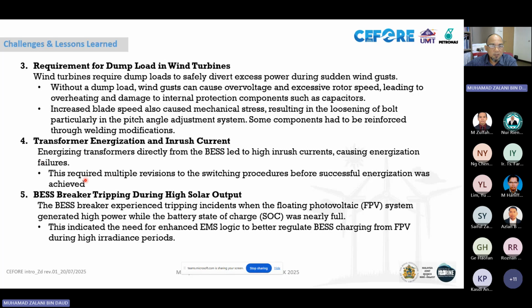Number 4 is about the transformer energization and inrush current. At the beginning of the commissioning stage, we need to energize the transformer. This transformer is a 500 kVA transformer, and we have the battery energy storage from MJB to energize this transformer. Inside the battery energy storage from MJB, they have an isolation transformer which is half the size of our transformer. So during energization, we failed. The system tripped during energization of the transformer. The system tripped multiple times.